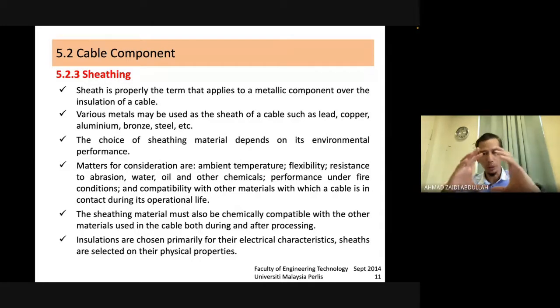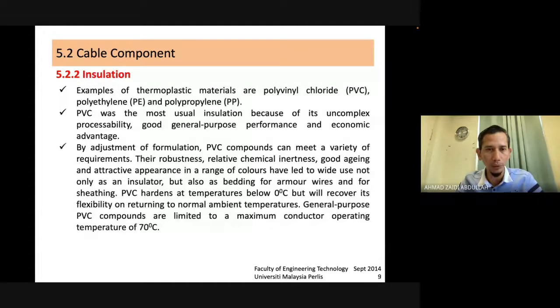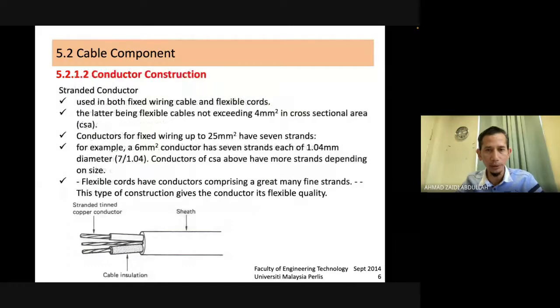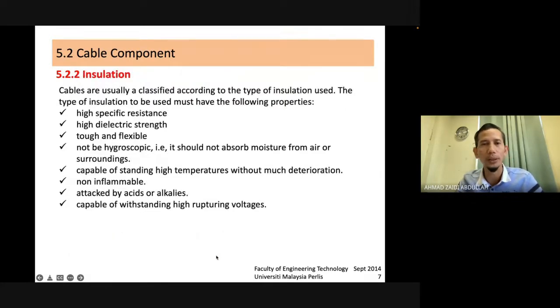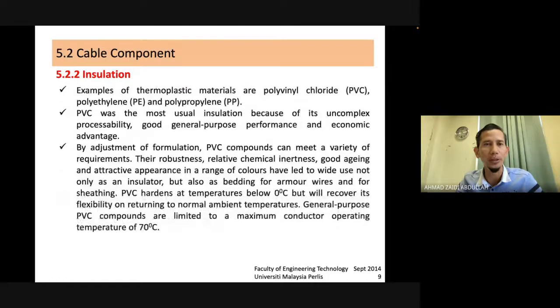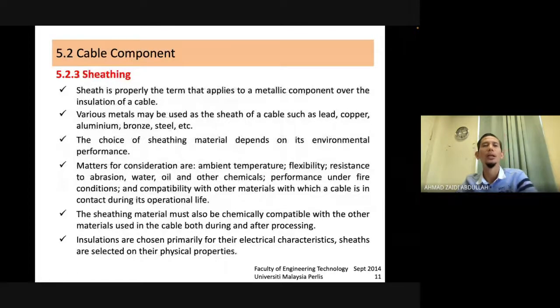Sheet yang kat luar tadi. Okay, kalau you can refer back to this, this is the sheet. Okay, the last one. Okay, we have a conductor, we have insulator, and the last one we have sheath. Kan as sheet tadi tu sheet. Sheath is properly the term that applies to the metallic component over the insulation of cable. So various metals may be used as sheath of cable such as lead, copper, aluminium, bronze, and steel.